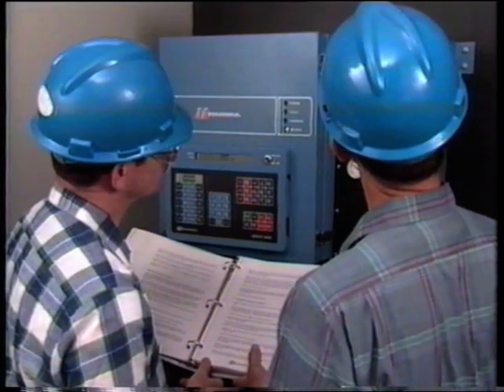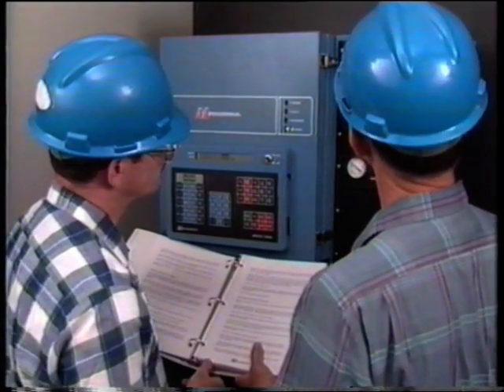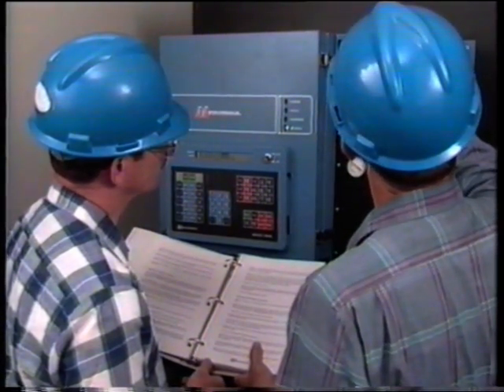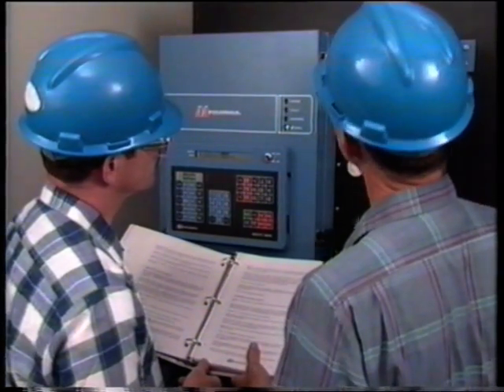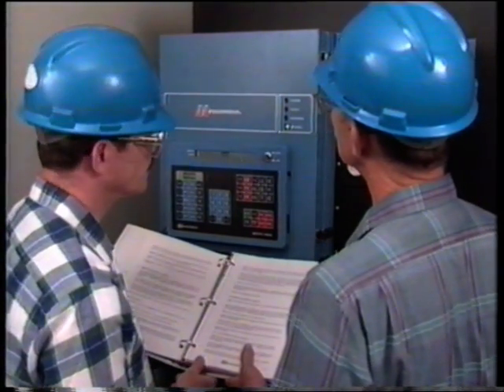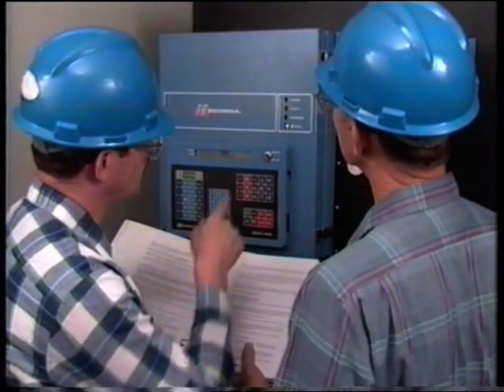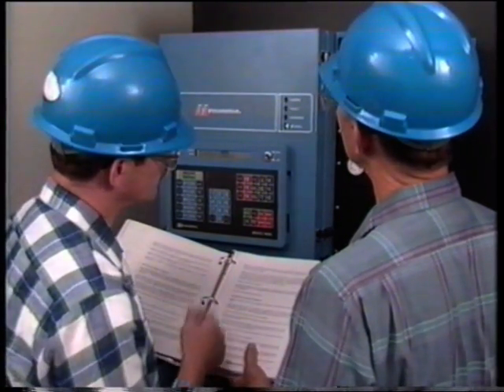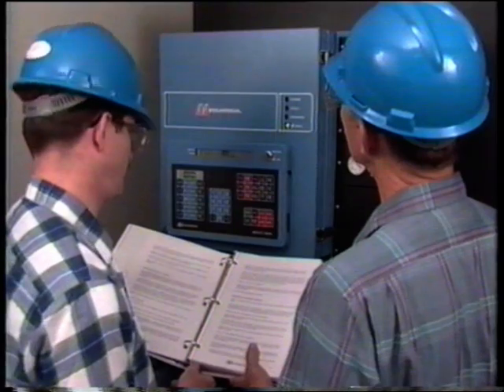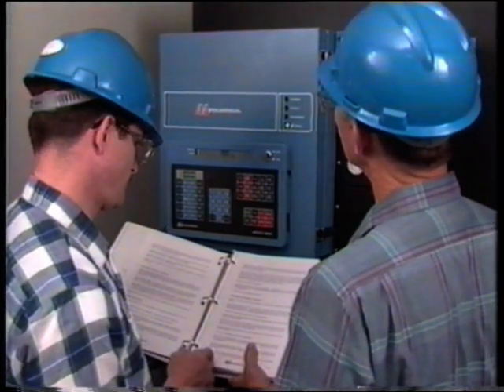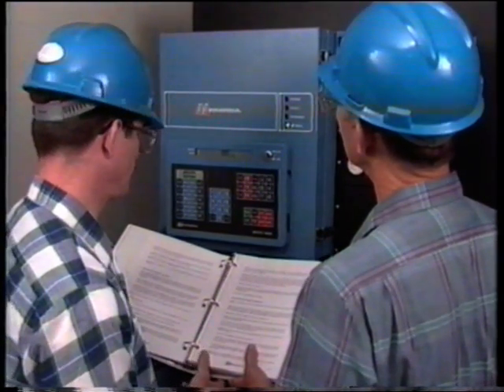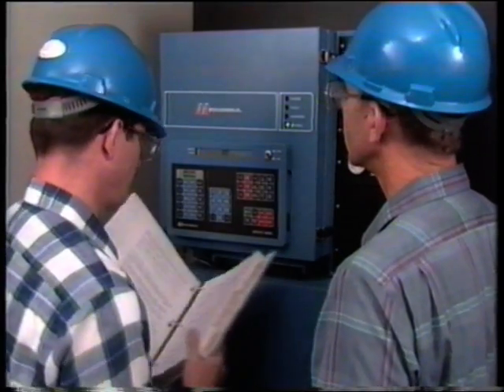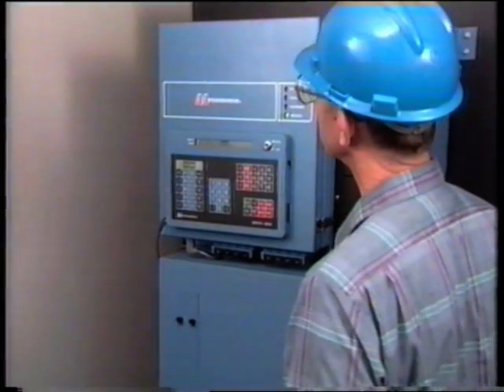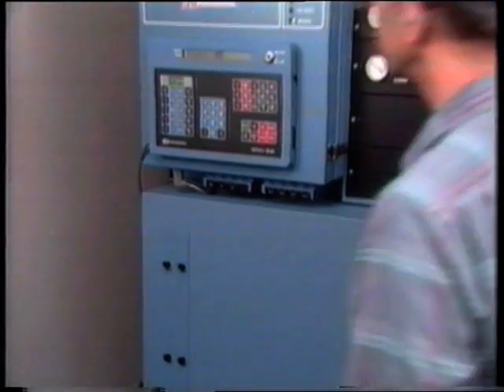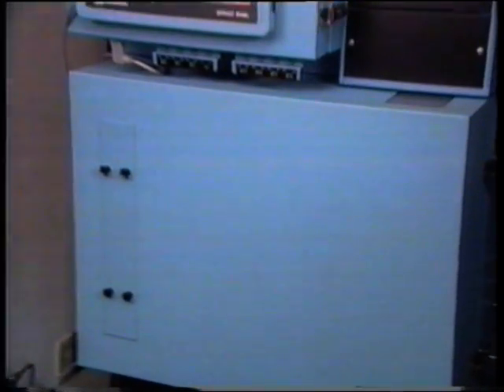Safety is a major consideration during oven maintenance. When maintaining a gas chromatograph, turn off power unless it's necessary for testing procedures. The process sample may be flammable or toxic, and the oven extremely hot. Before you begin, determine sample composition and any special safety requirements for hazardous locations. Also, notify control personnel of where and how long you'll be working, and obtain any required safety permits.